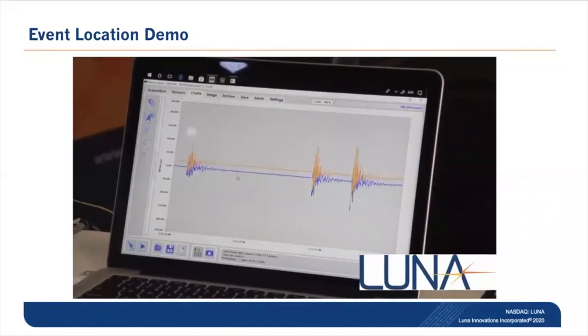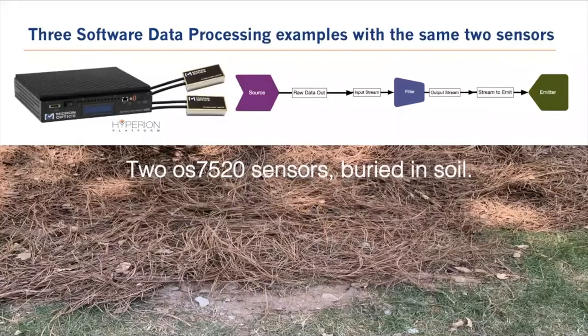Here's a demo from a previous trade conference using a 15-foot piece of PVC pipe collapsed into an S shape. Optical accelerometers are mounted on each end. In the data acquisition software, seven sections have been identified by the phase shift expected from the two sensors for an impact event. If you tap the pipe in the center, vibration travels equal lengths to both sensors arriving simultaneously. If tapped near one end, that sensor's signal leads the other significantly. The demo maps the phase shift to a musical note so you can hear the location detection capability.